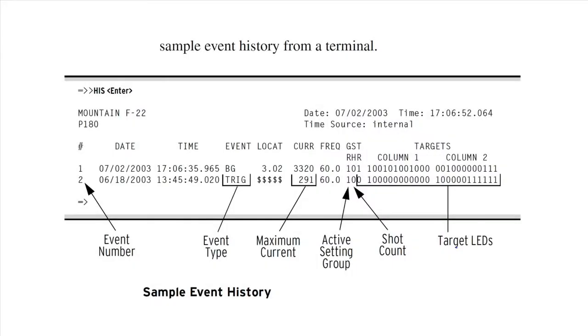Analyzing events. Reports. All reports are stored in non-volatile memory, ensuring that a loss of power supply to the SEL651R module will not result in lost data. Each time the recloser control generates a standard event report, it also generates a corresponding event summary.